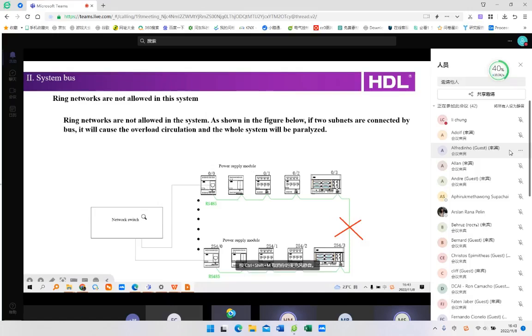So please do not make a ring topology. Each subnet can hold no more than 64 devices, but the last device of this system shall not connect with a device of another subnet. Then it will make a ring topology, and the system will be paralyzed.